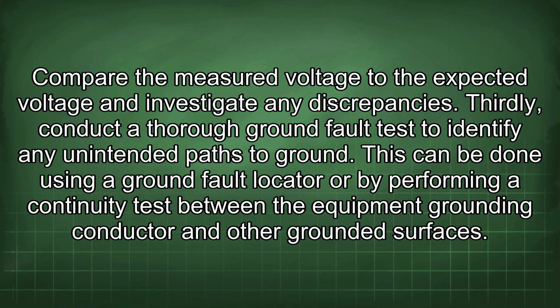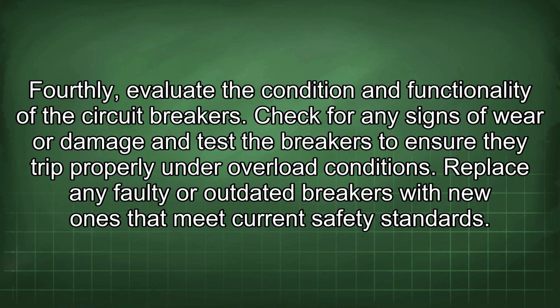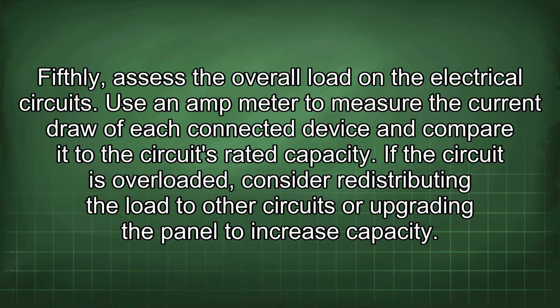and other grounded surfaces. Fourthly, evaluate the condition and functionality of the circuit breakers. Check for any signs of wear or damage and test the breakers to ensure they trip properly under overload conditions. Replace any faulty or outdated breakers with new ones that meet current safety standards. Fifthly, assess the overall load on the electrical circuits. Use an ammeter to measure the current draw of each connected device and compare it to the circuit's rated capacity. If the circuit is overloaded, consider redistributing the load to other circuits or upgrading the panel to increase capacity.